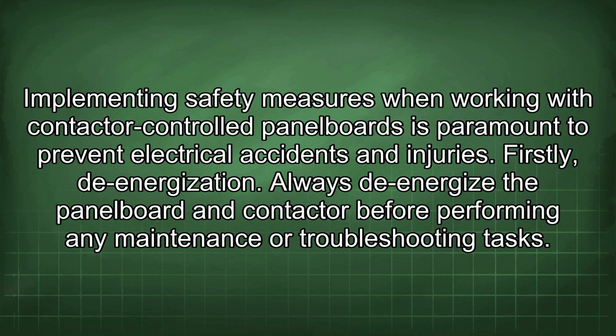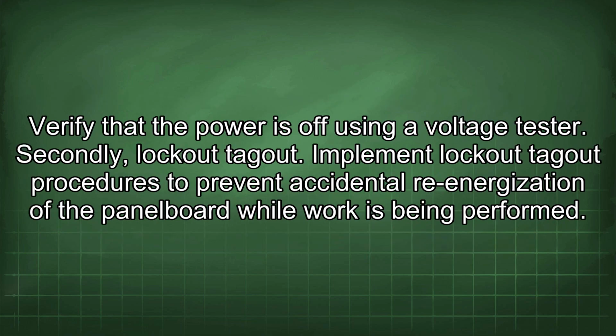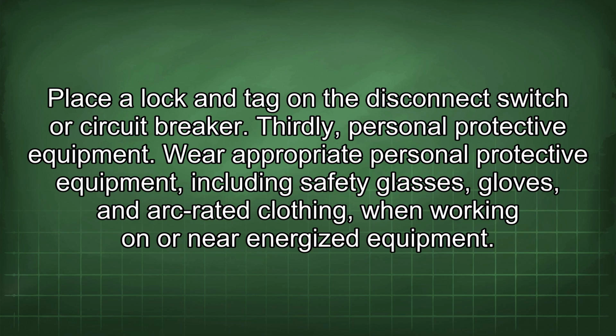injuries. Firstly, de-energization. Always de-energize the panel board and contactor before performing any maintenance or troubleshooting tasks. Verify that the power is off using a voltage tester. Secondly, lockout-tagout. Implement lockout-tagout procedures to prevent accidental re-energization of the panel board while work is being performed. Place a lock and tag on the disconnect switch or circuit breaker.